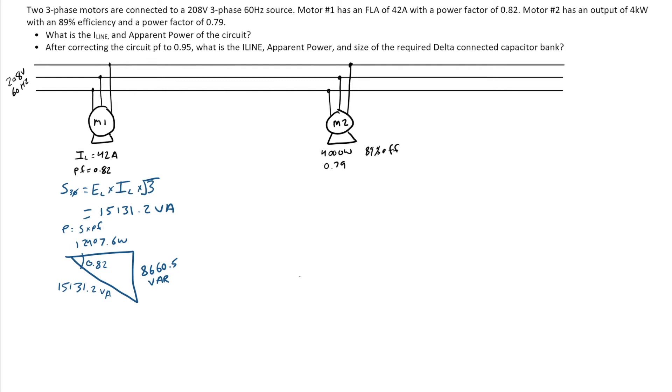So what I'm going to do is on motor two, I'll switch to red here. In order to get my power input, I'm going to go power output divided by my efficiency. So in this case, 4,000 watts divided by 0.89 or 89%. That gives me an input to the motor of 4,494.4 watts.